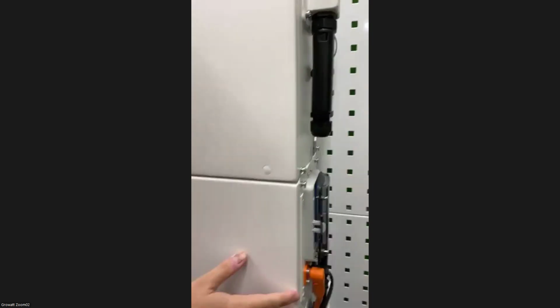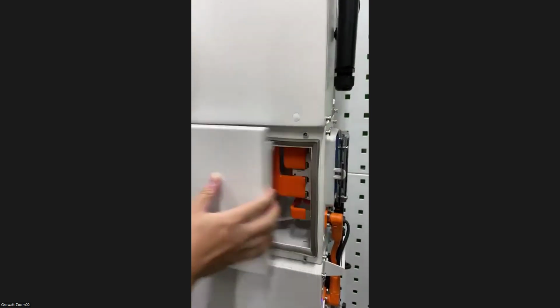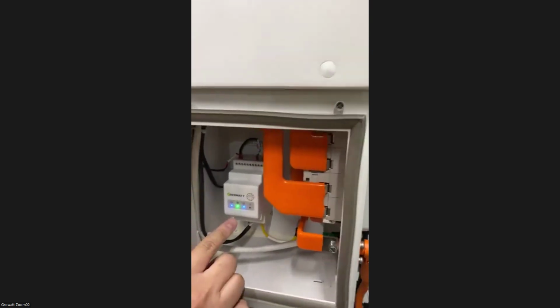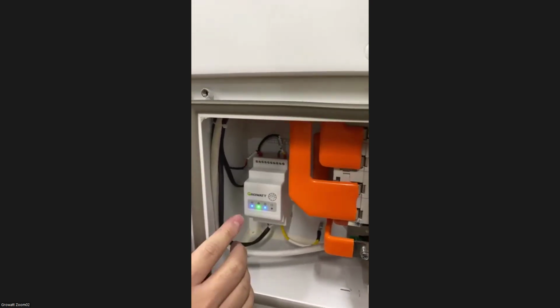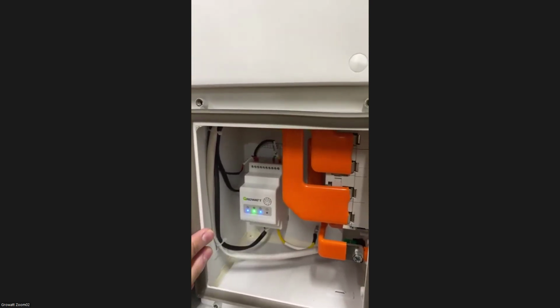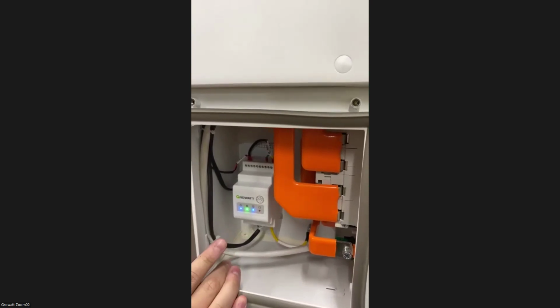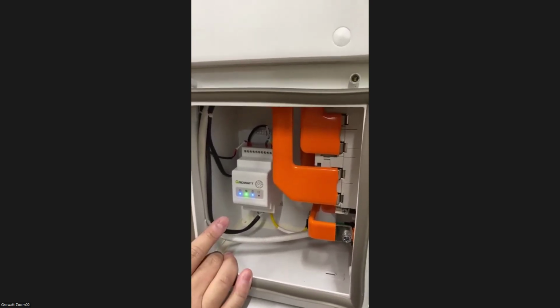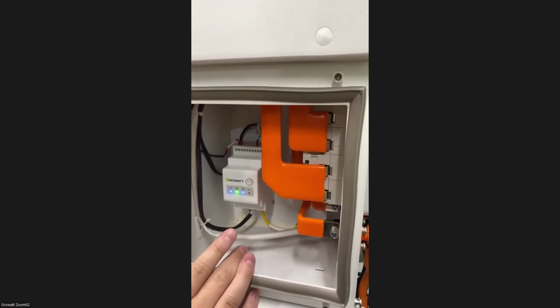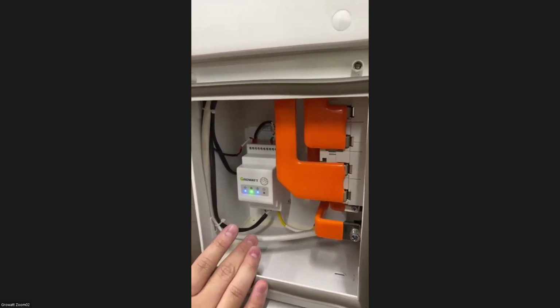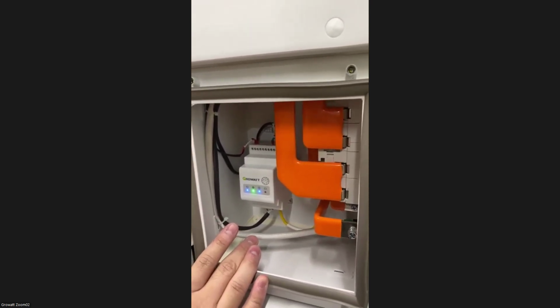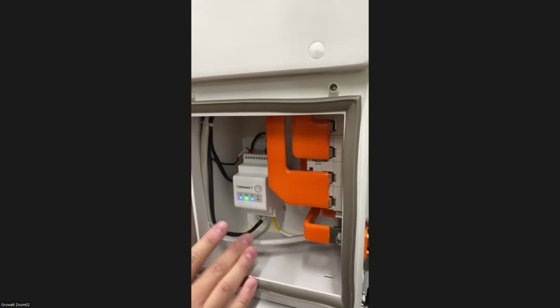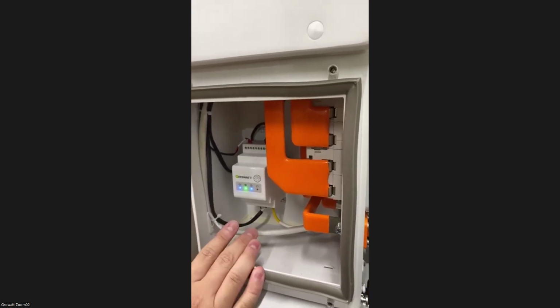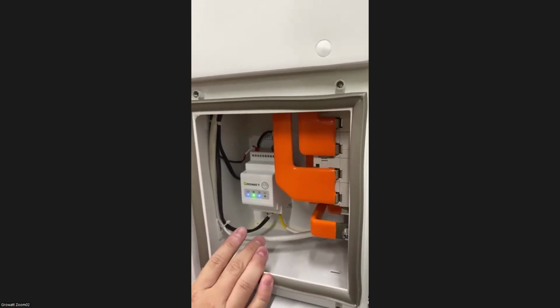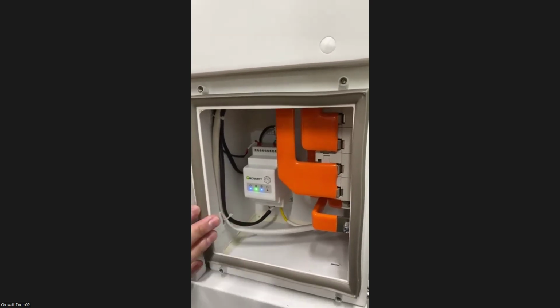Here I'm going to show you where the inbuilt meter is located. This is where the inbuilt meter is located, and it will come by default inside. Remember, as I said on my slides earlier, if the CT is within 10 meters, you don't need an external one. If the CT is more than 10 meters from the inverter, you need an external meter. And if you're using this as an AC coupling system, with a single phase inverter already on the side, you will also need an external smart meter.